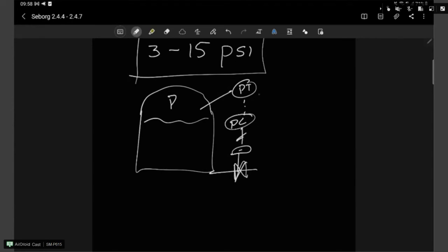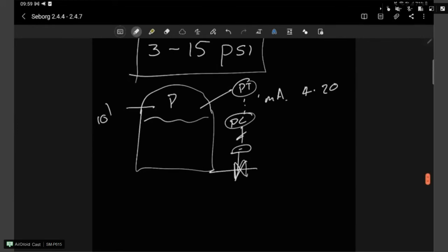This measuring instrument provides a milliamp signal out, which is just the standard range. If it's in the range of 4 to 20 milliamps, and the range of this pressure could be between 10 bar and 1 million, just to be interesting, a value of 4 milliamps relates to 10 bar, and a value of 20 milliamps would relate to 1 million bar. And this signal then, a 4 milliamp signal, if it acts similar, I'm not going to confuse you with this.